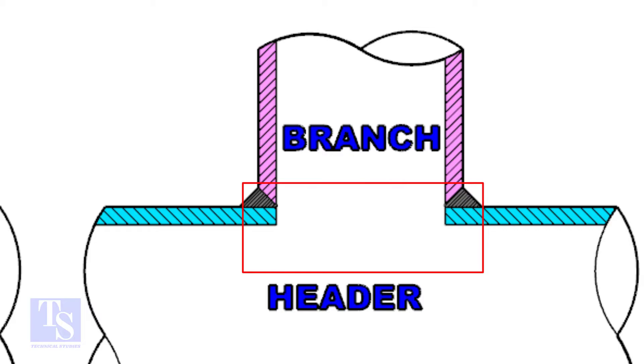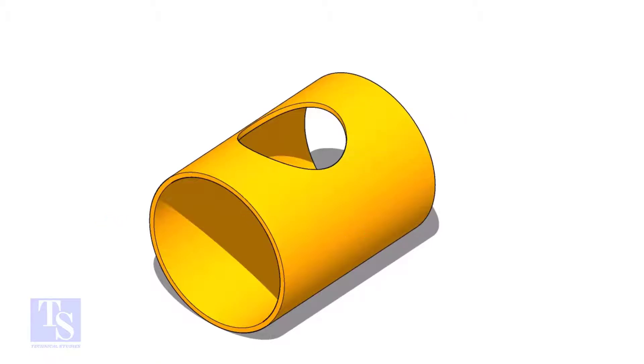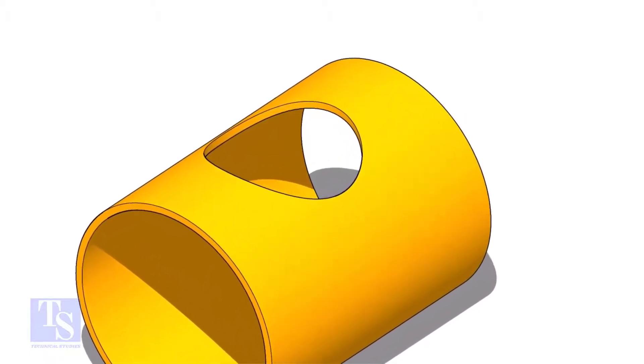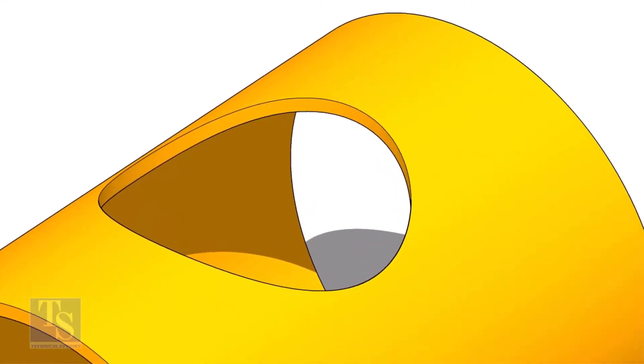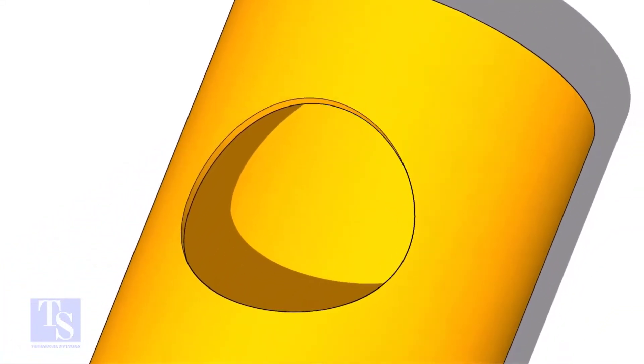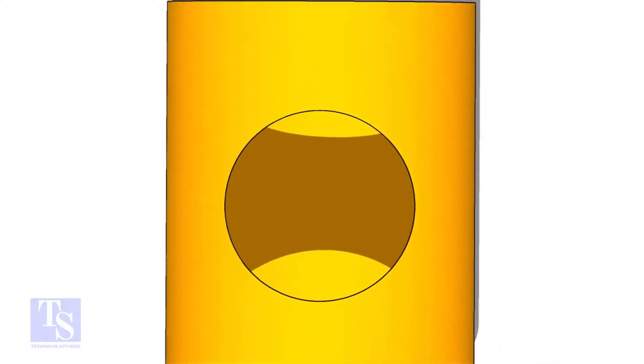And on the header pipe, a hole is there. The diameter of the hole on the header pipe is the same as the inside diameter of the branch pipe. Stub-on connections are given when the header and the branch pipes are of the same size or the branch pipe is only one unit less than the size of the header.